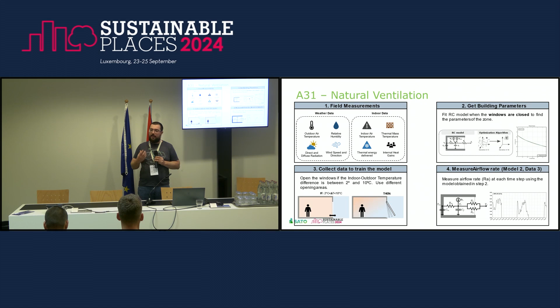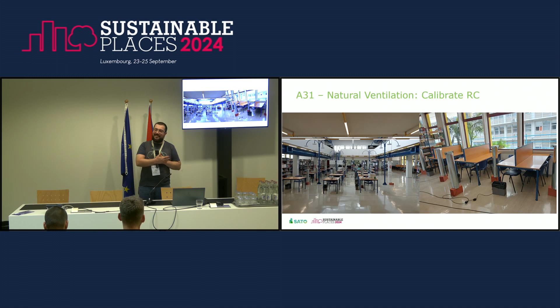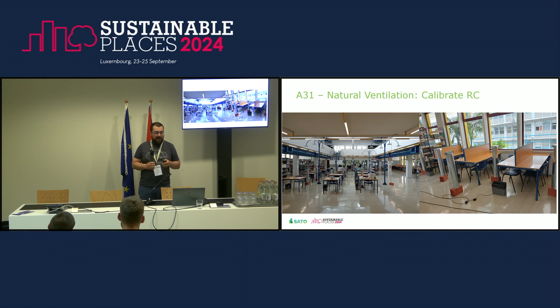I'm going to show you some pictures of our experiments. This is the inside of the library. These cylinders are there to mimic the heat flow of people. We did this when the building was unoccupied so we could fully control the behavior of indoor loads. These represent the heat of people, about two-thirds to three-quarters of maximum occupation, and we used this to calibrate the RC model of the building.